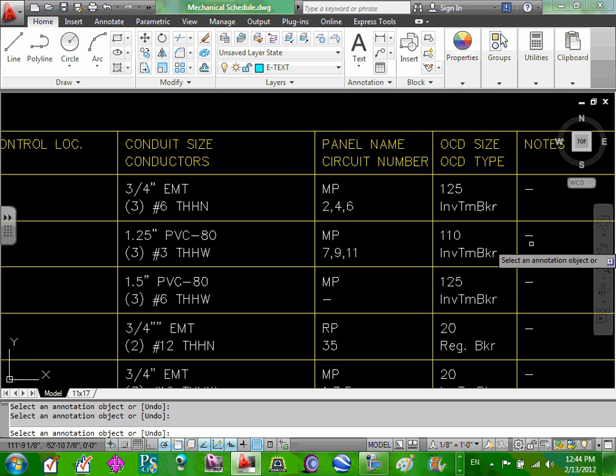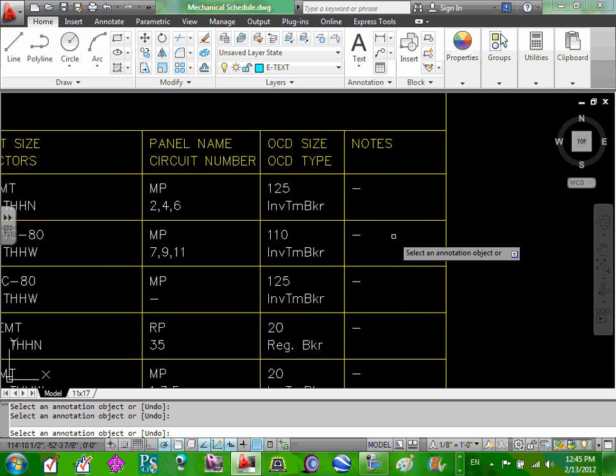They're saying 110 fuse, but I don't have a fuse panel though. So what I'm going to end up doing, I will put a 110 amp circuit breaker here and move all the way right next to the equipment, put my disconnect here. The disconnect will have a 110 amp fuse and feeder. That's what we're doing. Because they say the fuse, and I can't put a fuse in a panel that has circuit breakers. So, long story short, you end up sizing 110 with a 110 amp circuit breaker to protect your feeder. Right next to the equipment, you throw a fused disconnect, and the fuse will be 110. As far as you're concerned, it's going to be 110. Okay. Any other notes? You add it here.